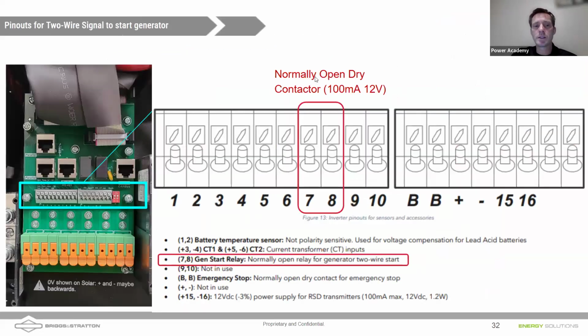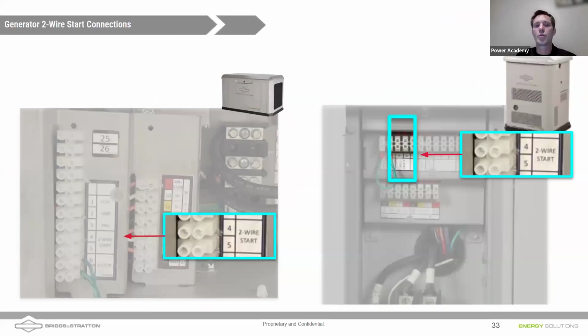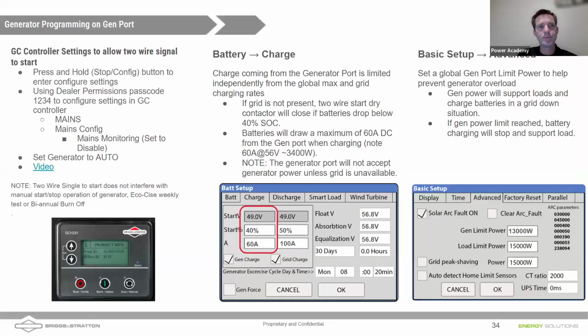How do you do that generator integration? You'll use pins 7 and 8 on the comms board. Those are the two-wire start signals. That's a normally open signal. You can run that directly into pins 4 and 5 on our Briggs and Stratton generators. So if you're using a Briggs and Stratton generator, you can run it right into pins 4 and 5.